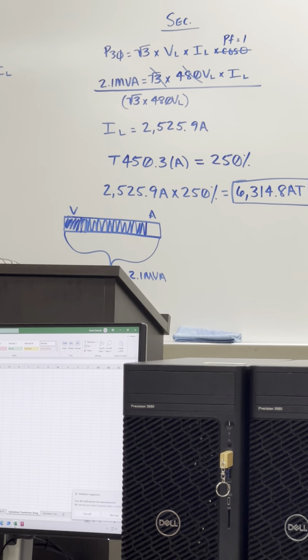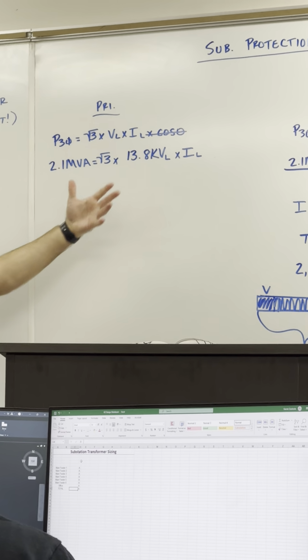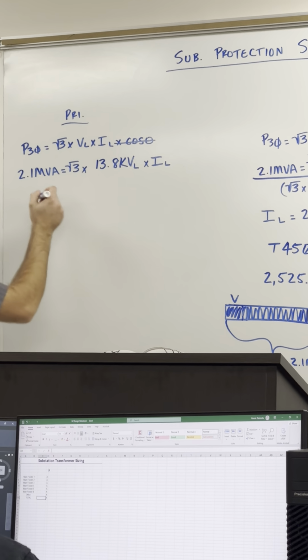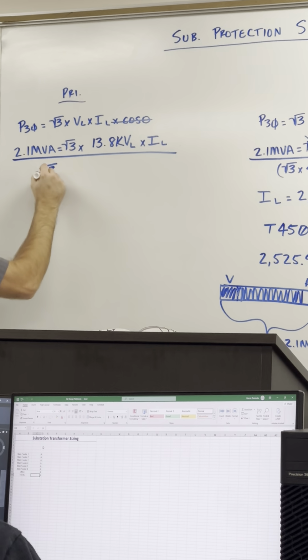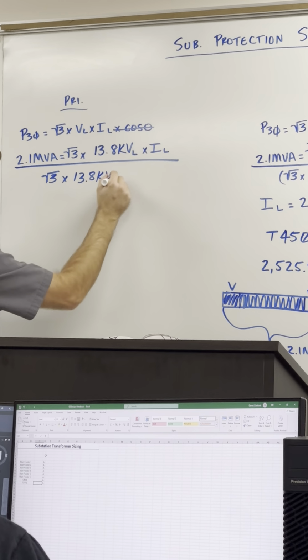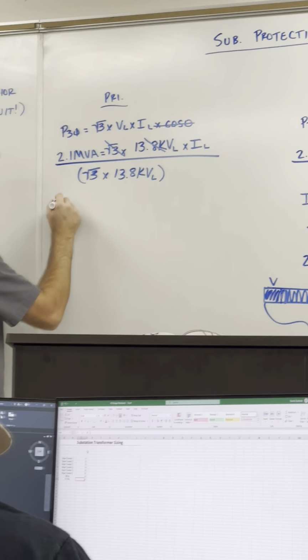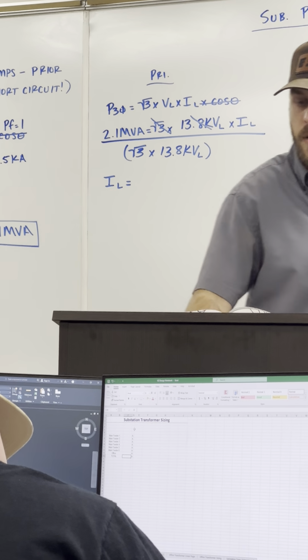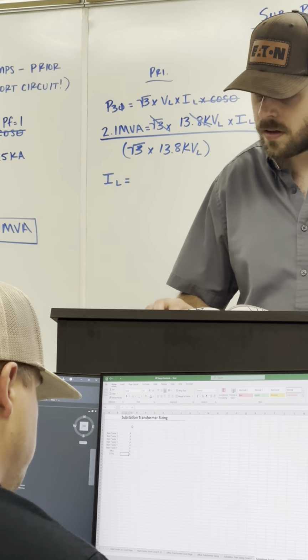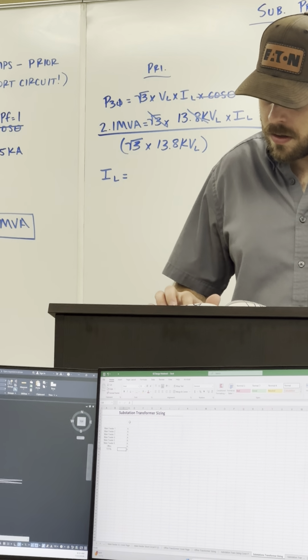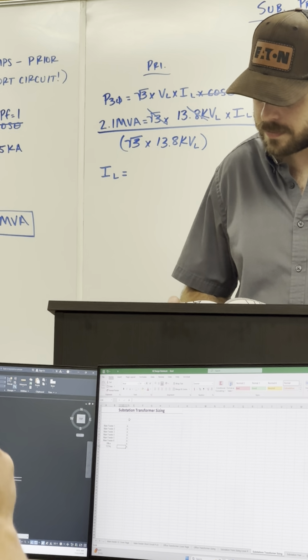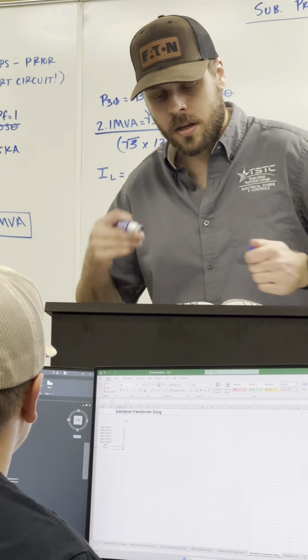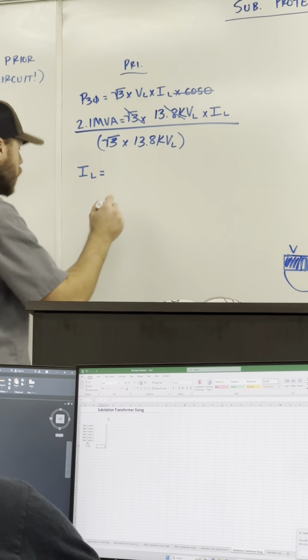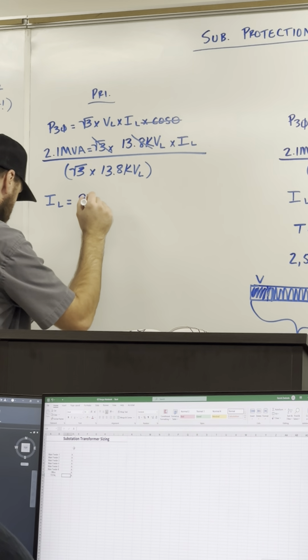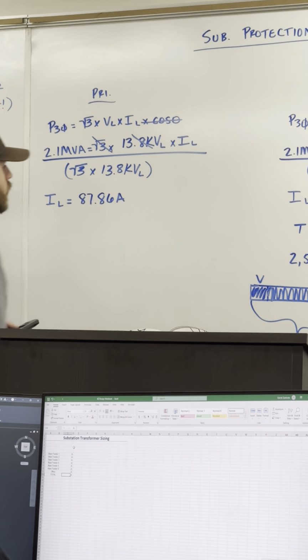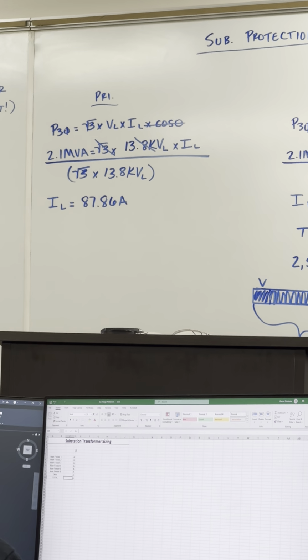So there are some little pre-checks you can start running in your mind. If we calculate something really high on this side, we maybe punched something in our calculator wrong. But it's going to be the same process. We're going to take both sides and divide them by square root of 3 times 13.8 kilovolts. Again, don't forget parentheses. These will cancel out on that side. And I get 87 point, we'll just call that 86 amps. So a lot lower.